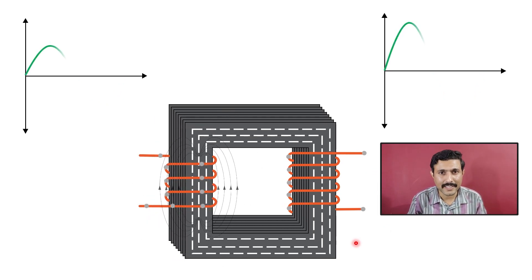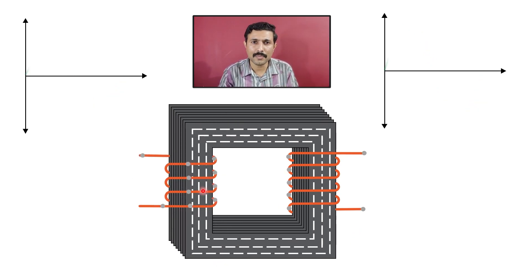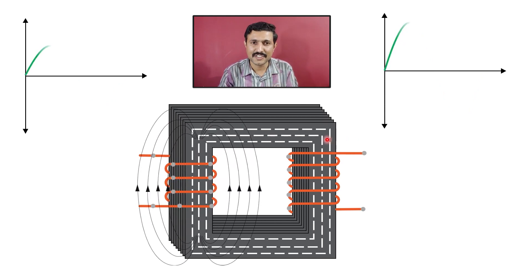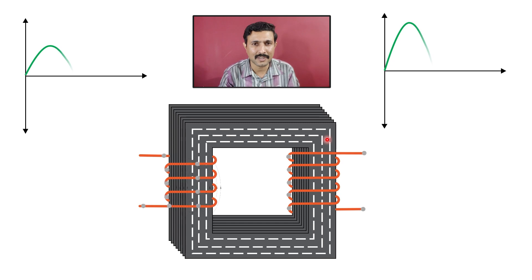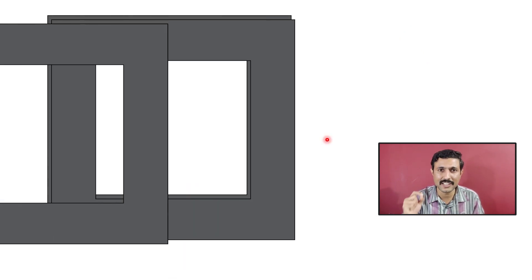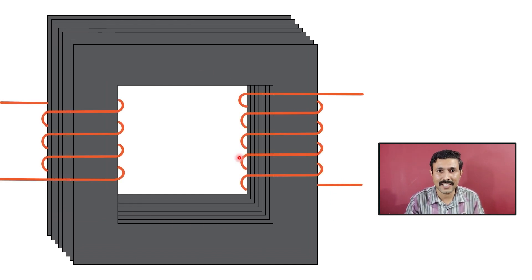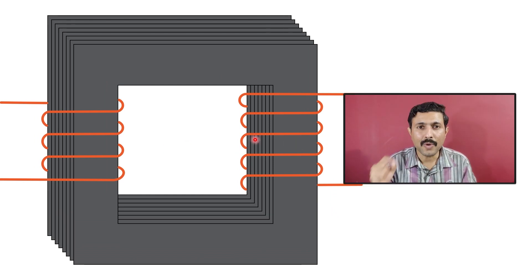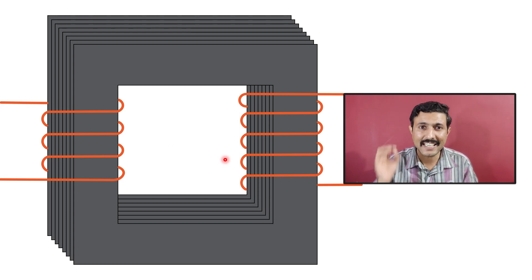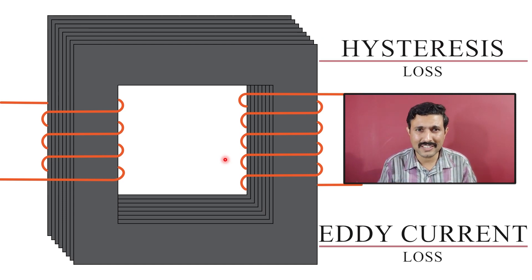EMF is induced not only in the winding but also in the core, which causes power losses in the core. To avoid those power losses, the core material is chosen appropriately. Generally, silicon steel is used as the core material. Thin laminated sheets of silicon steel are stacked together to create the core, and then winding is wound on both the primary and secondary sides. The reasons behind these choices relate to hysteresis loss and eddy current loss.